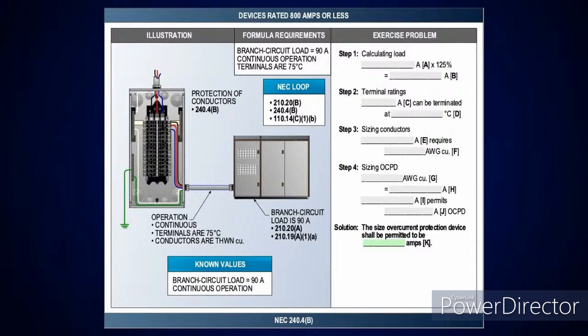Well, here's a good one. Branch circuit load's 90 amps. It's continuous load, and you'll see in the formula requirements you're going to size it based off 75 degree C terminals for your homework. All right.